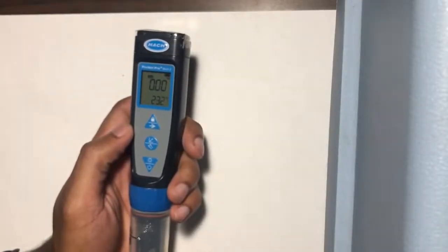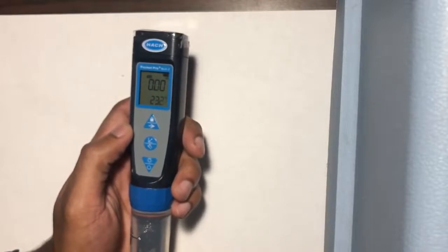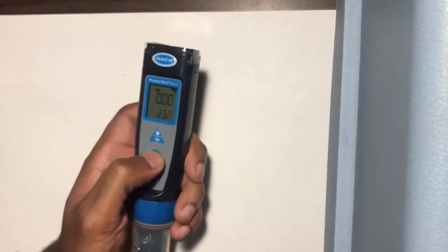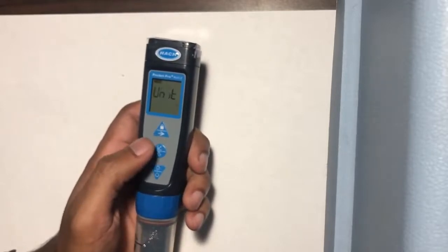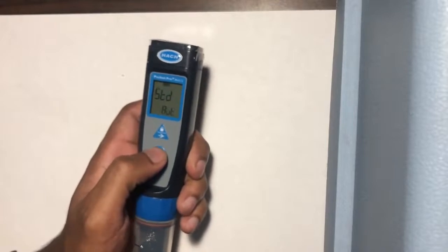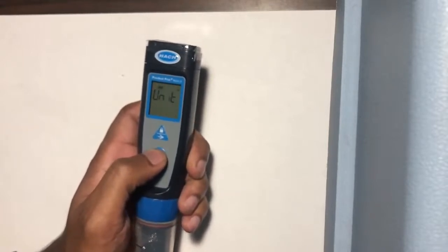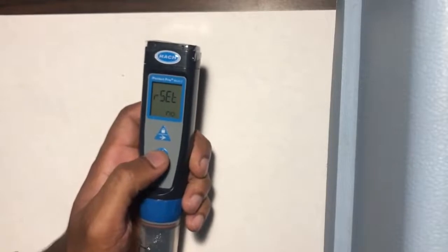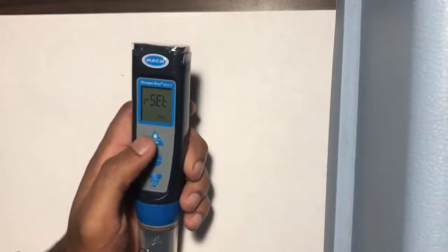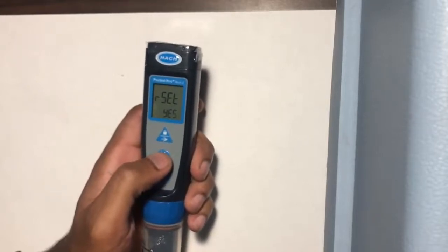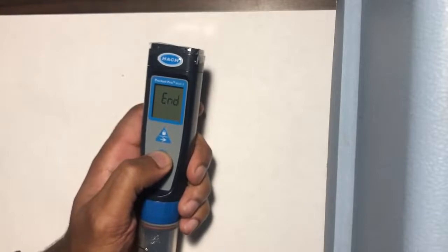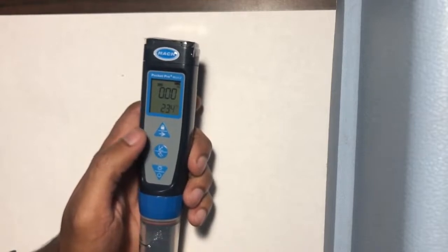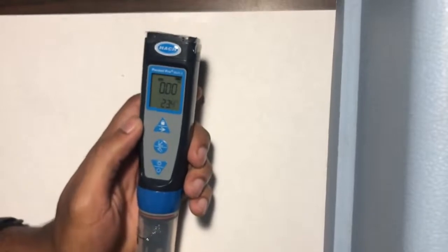As I said, this will change these settings back to factory. If you're still having difficulty and the Hach refuses to cooperate, try giving it a hard reset. To reset, hold down the middle button to enter settings mode. Once in settings mode, tap the middle button until you reach RSET. Tap the top or bottom button to scroll up to YES, and hold the middle button until you see END. This will reset all the units, parameters and scales back to factory settings, which we use by default anyway, minus the ECAL setting, which you should probably go back and change.